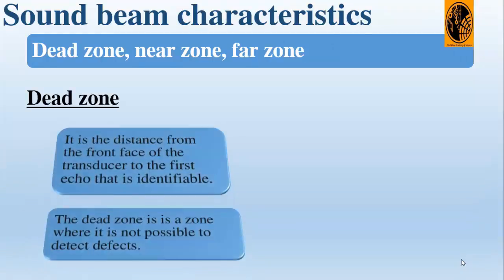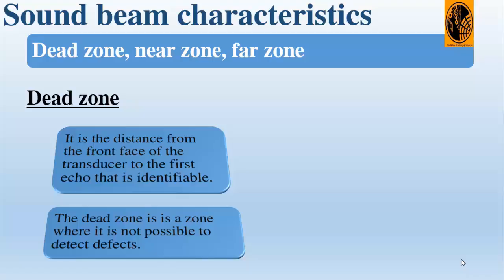Let's start with the dead zone. It is the distance from the front face of the transducer to the first echo that is identifiable. The dead zone is a zone where it is not possible to detect defects.